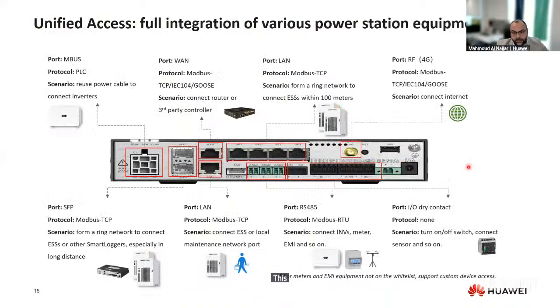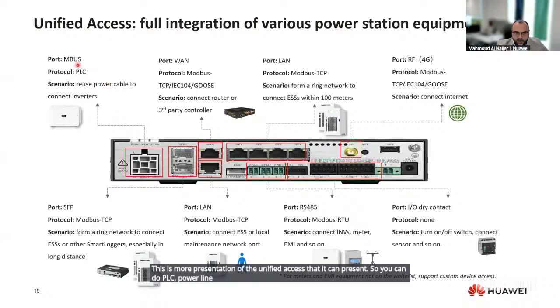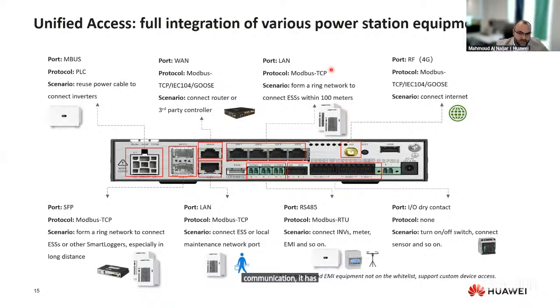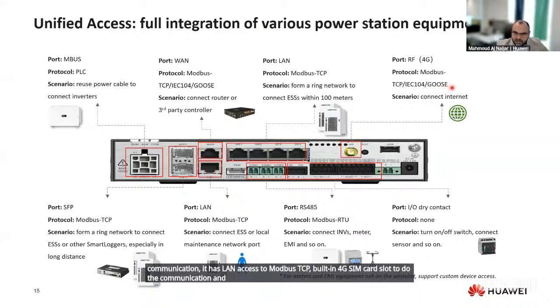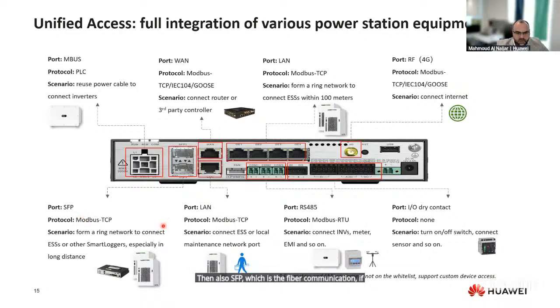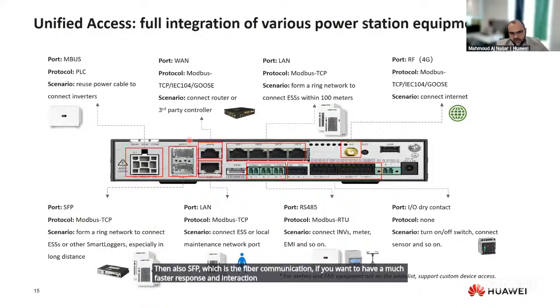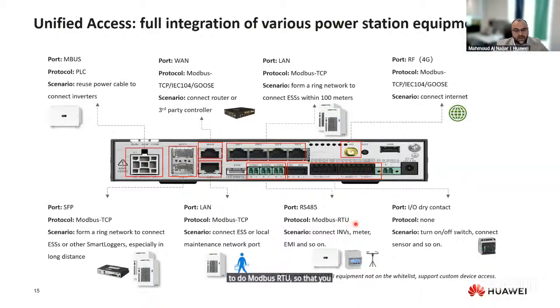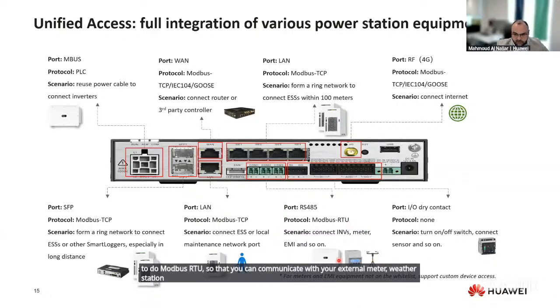This is more of a presentation of the unified access that it can provide. So you can do PLC power line communication through Modbus to the inverters. It has Modbus communication, Modbus TCP, IEC 104 and GOOSE communication. It has LAN access to do Modbus TCP, and a built-in 4G SIM card slot to do the communication and have online access to remote monitoring. Then also SFP, which is the fiber communication, if you want a much faster response and interaction. So it has built-in fiber ports, and it also has RS485 communication to do Modbus RTU, so that you can communicate with your external meter, weather station, sensors, and third-party inverters.